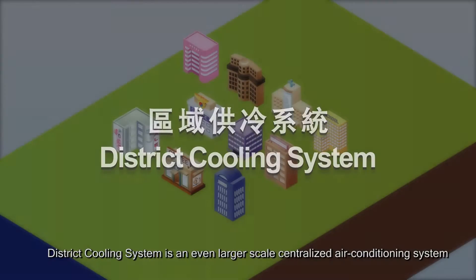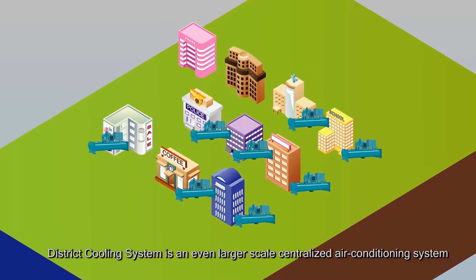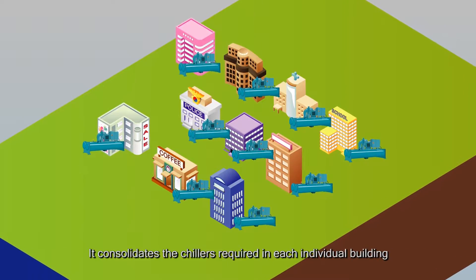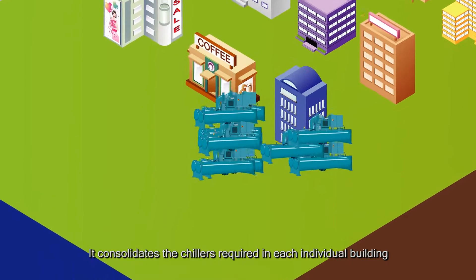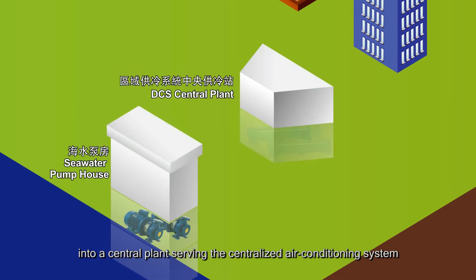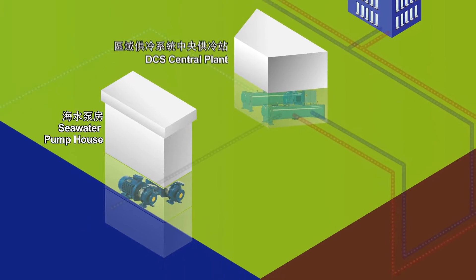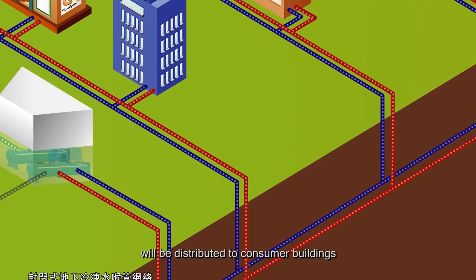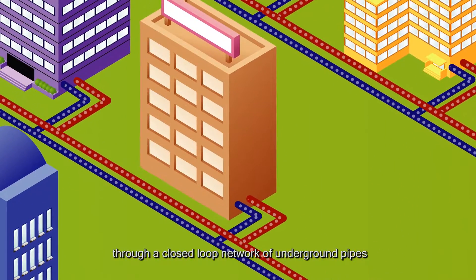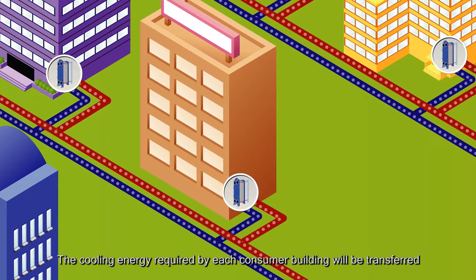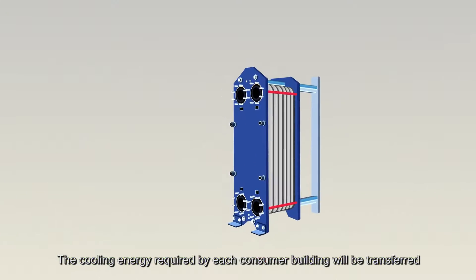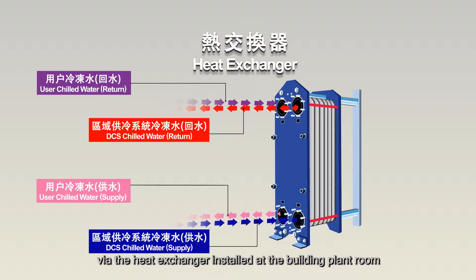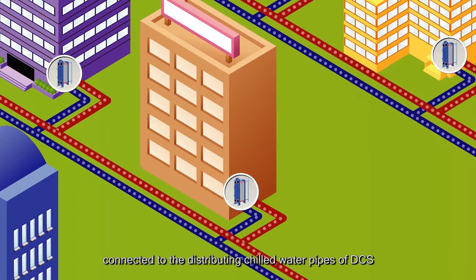What is a District Cooling System? A District Cooling System is an even larger scale centralized air conditioning system. It consolidates the chillers required in each individual building into a central plant serving the centralized air conditioning systems of buildings in the district. The chilled water produced at the central plant is distributed to consumer buildings through a closed loop network of underground pipes. The cooling energy required by each consumer building is transferred via a heat exchanger installed at the building plant room, connected to the distributing chilled water pipes of the DCS.